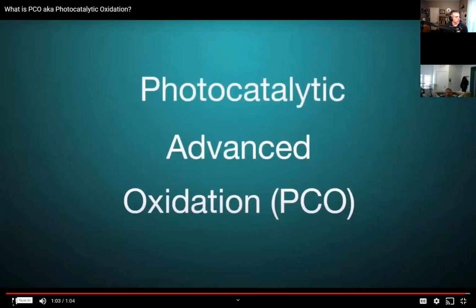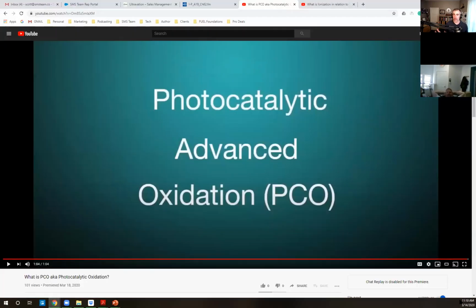All right, so the short skinny on that video is simply, you can have just regular UVC technology, actually UVGI technology with UVC lamps in an HVAC system. And then you can level it up by adding in PCO like this. The advantage of the PCO process is that it is literally, as they use the term in that video, creating a field around the device. So as the air is passing through it, besides being attacked by the UVC light coming off of the lamp, you're also gaining this invisible PCO field that is created from that reaction process. And that helps break things down, like VOC molecules and other airborne contaminants.